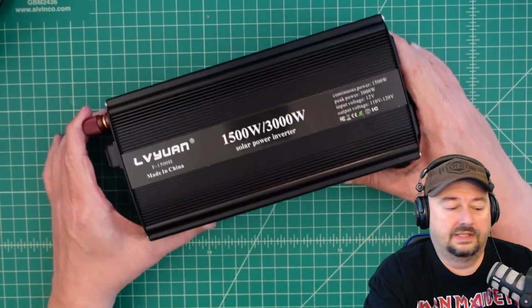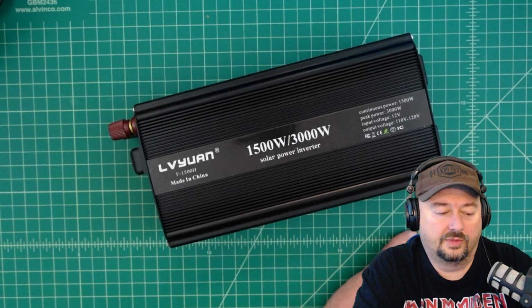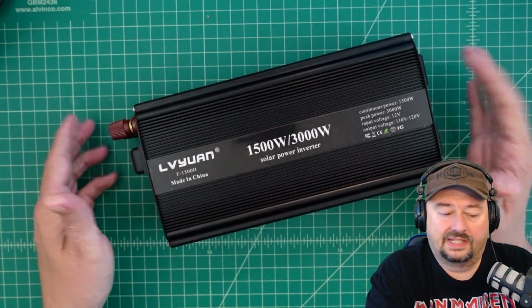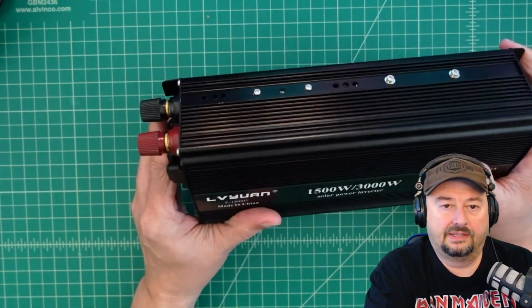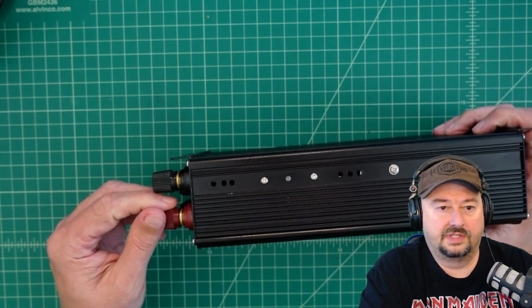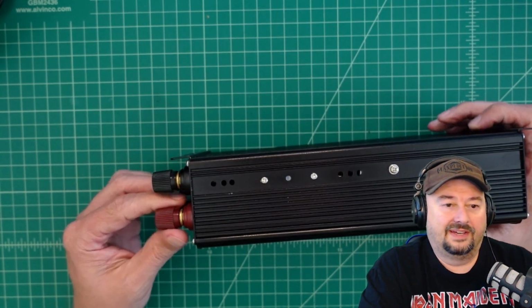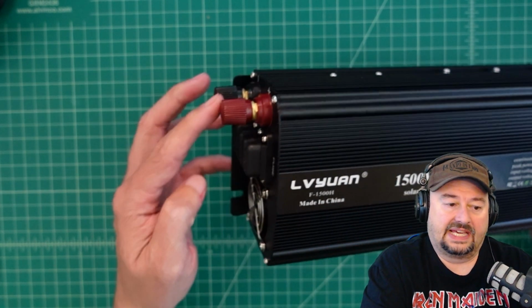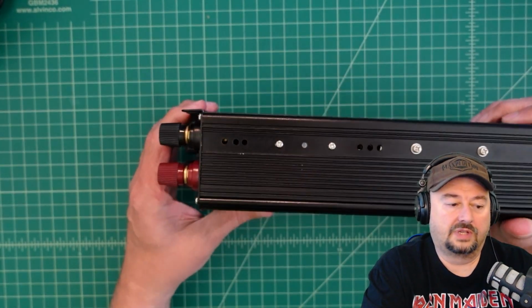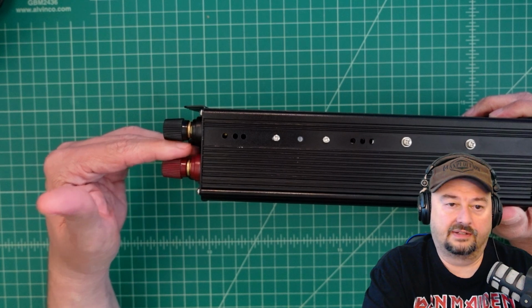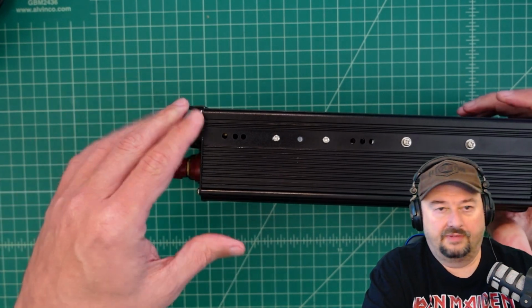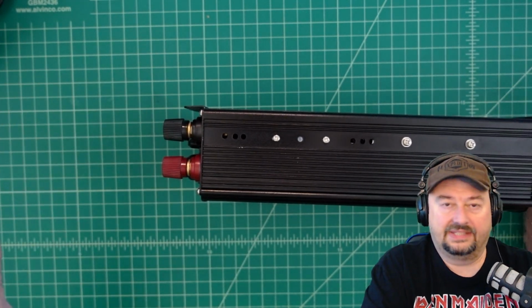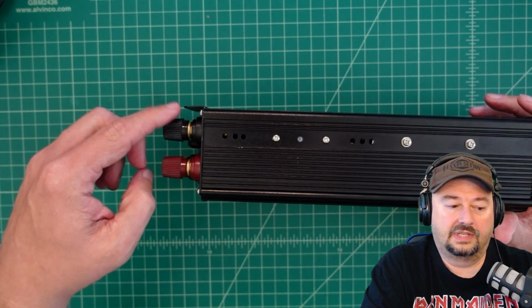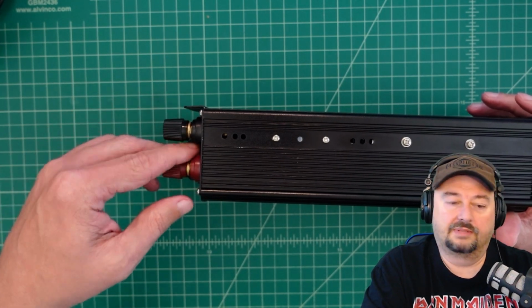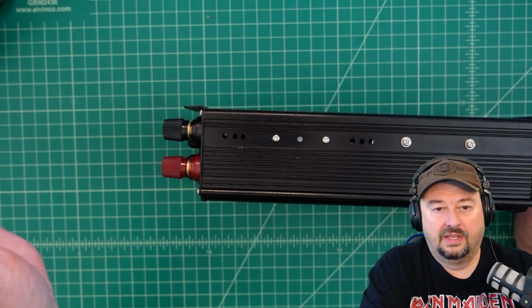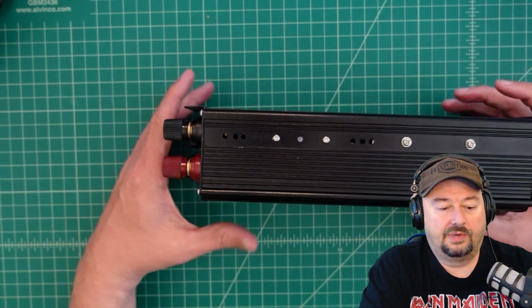Let's talk a little bit about the inverter and what we saw. There's a couple of things I like and didn't like. It's very common for these lower priced inverters to just have connectors like this. I prefer to have them on either side of the inverter, or have some sort of plastic blocker in the middle, so you don't have to worry about accidents happening, like connections bumping into each other and causing a discharge. So that's one thing I'd mention.